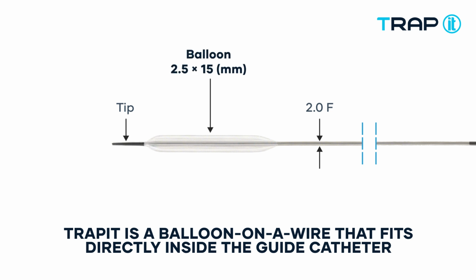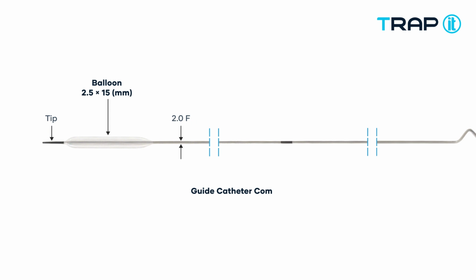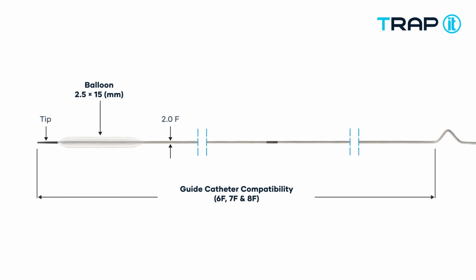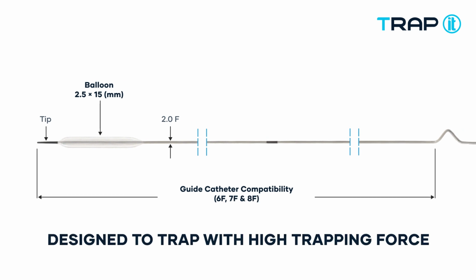Second, the balloon it has is a 2.5 by 15. It is suitable for trapping in 6, 7, and 8 French guides, and the balloon does not have a hydrophilic coating that can be slippery and reduce the friction with the wire. So by using this specific balloon, there can be more force applied to the guide wire.